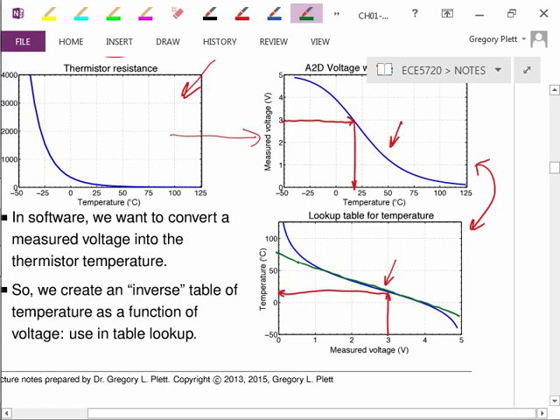We can see this is linear from about there to there, quite linear. So from about 50 degrees down to about 0 degrees, I'd have quite accurate readings simply using a linear function. However, if I had cold temperatures, that would not work as well. So that's a design decision you have to make: memory storage and computation complexity trade-off versus accuracy. But that's the basic principle of how you use a thermistor to infer temperature.